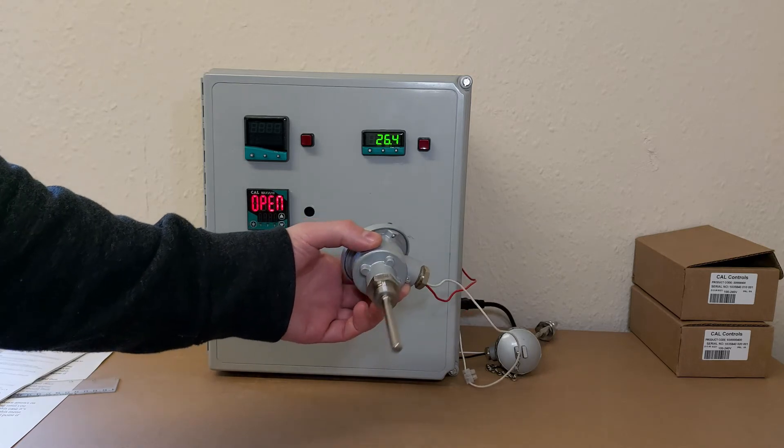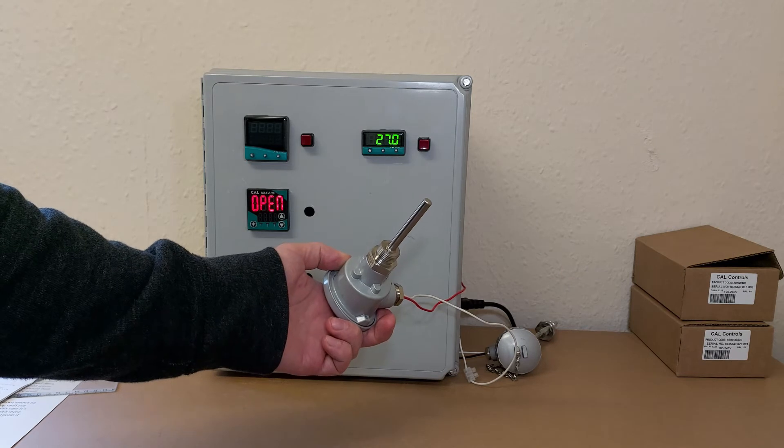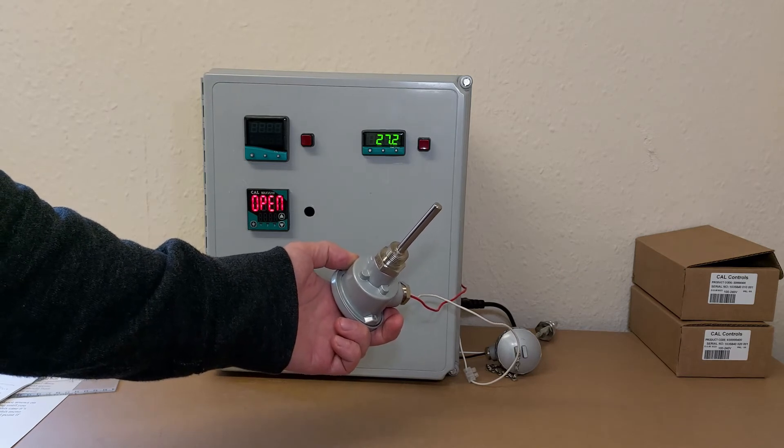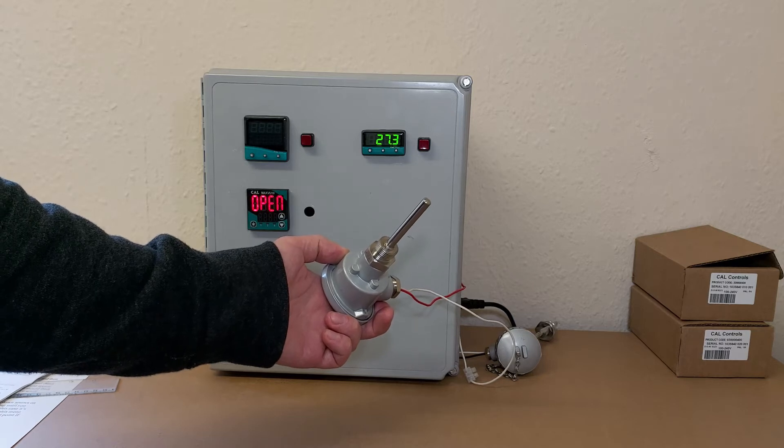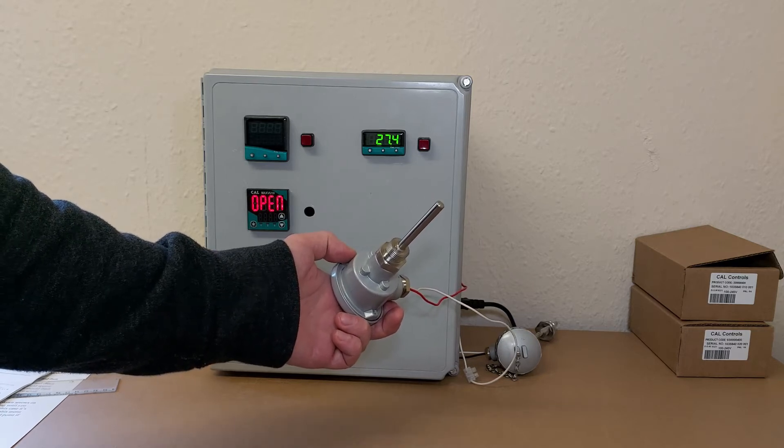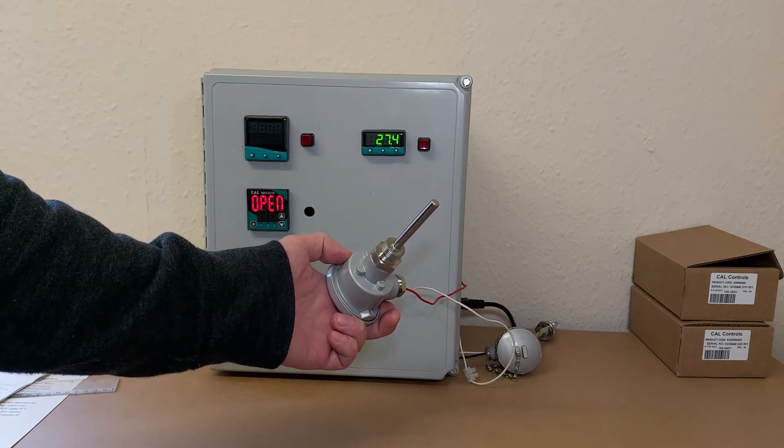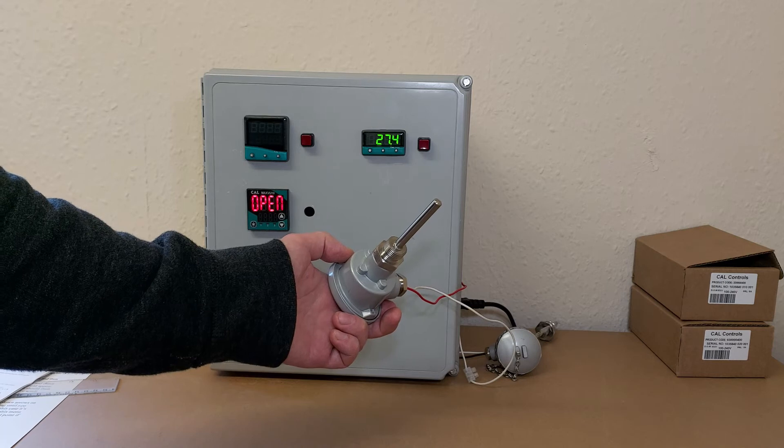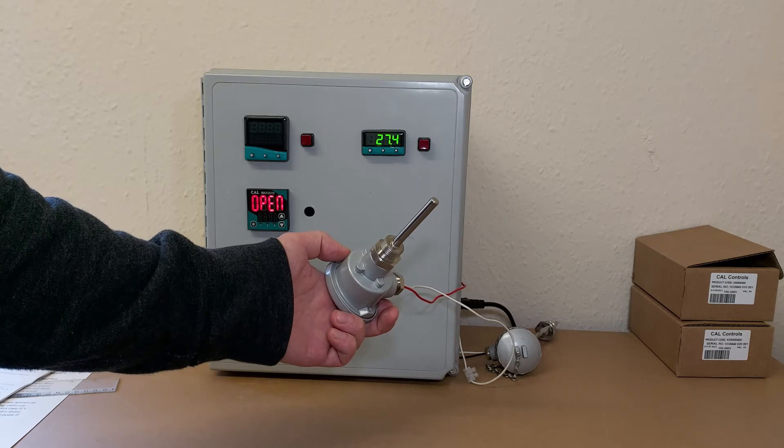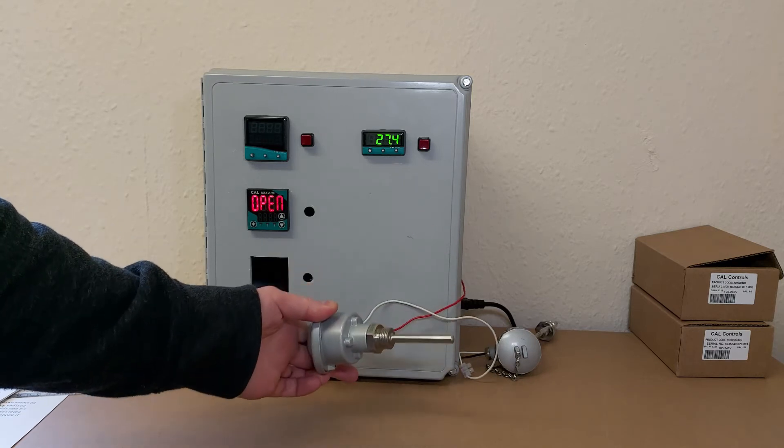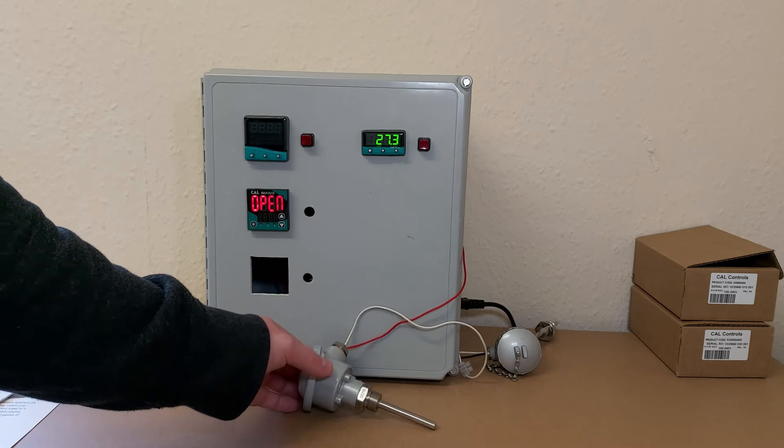It has a platinum element and a resistance of 100 ohms at 0 degrees C. Other types of RTD are available, for example PT1000, which has a resistance of 1000 ohms at 0 degrees C. RTDs using copper and nickel wire are also available. CAL controllers can only be used with the PT100 type of RTDs.